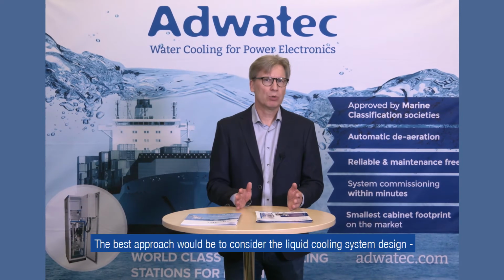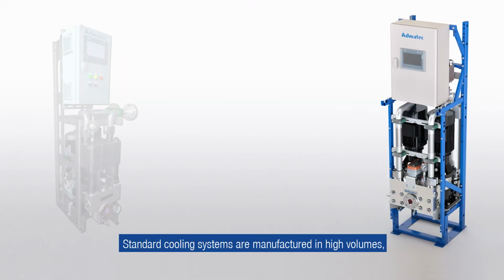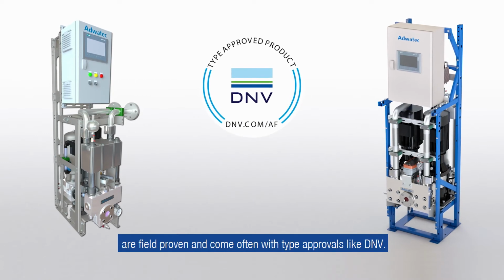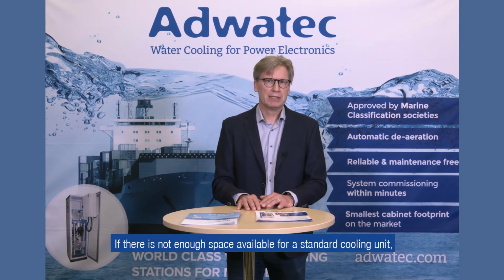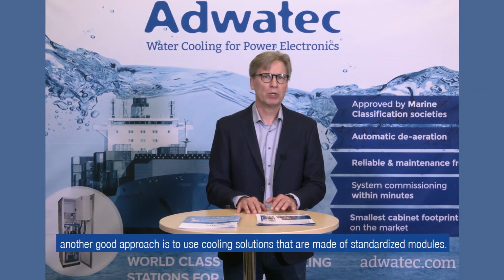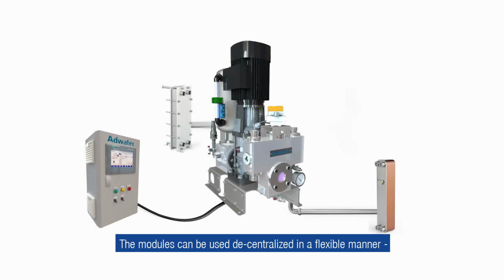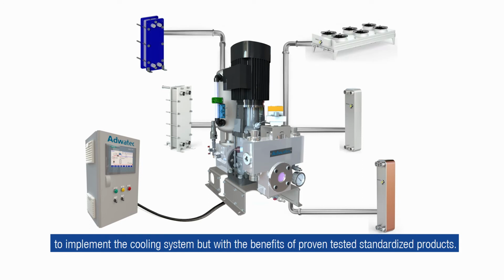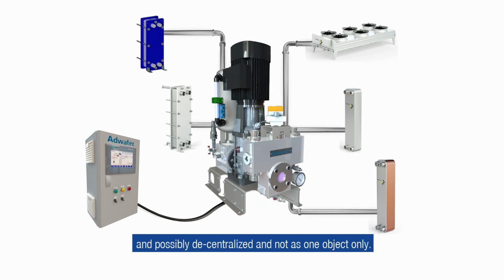The best approach would be to consider the liquid cooling system design at an early stage in the engineering process. This way, standard cooling solutions available in the marketplace could be used and fitted to designs as such. Standard cooling systems are manufactured in high volumes, are field-proven, and often come with type approvals like DNV. If there is not enough space available for a standard cooling unit, another good approach is to use cooling solutions that are made of standardized modules. The modules can be used decentralized in a flexible manner to implement the cooling system, but with the benefits of proven, tested, standardized products. This way, the system could be fitted to meet the height and width requirements and possibly decentralized and not as one object only.